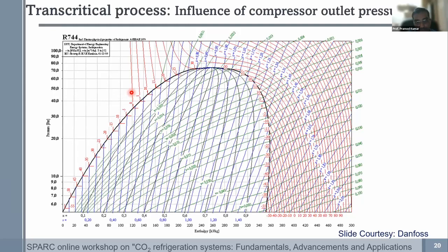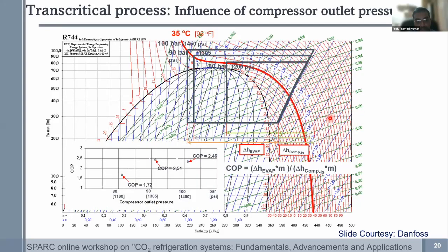I'm sure that tomorrow or the day after, Mr. Kamath from Danfoss will also talk a little bit more on the controls. But this just tells you that as you keep increasing the pressure, the COP of the system goes up to a certain pressure, and then this is the knee of the isotherm. If you go beyond this, you get a diminishing return. The amount of cooling effect relative to the power going into the compression becomes significantly small. Fortunately, all of these have been programmed in most standard controllers available for carbon dioxide, so you don't have to split hairs over how to select the optimum pressure.